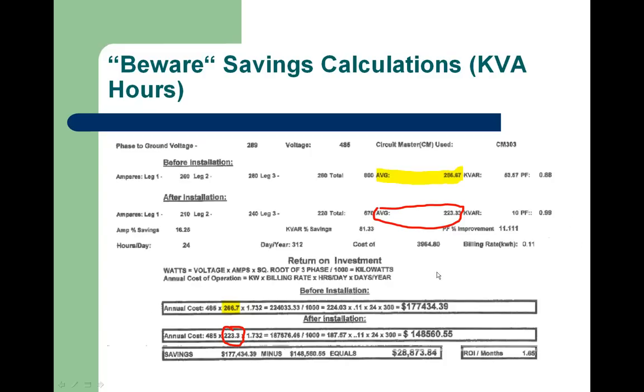The problem was that they were basing their savings on volt-amps, or kVA, and not watts or kilowatts. So the calculation that they have was based on this 266 amps, highlighted in yellow here, times the factor for three-phase. And you'll notice up here with the watts, voltage times amps times the root of 3 divided by 1,000 is kilowatts; they didn't show the power factor in there. So consequently, they calculated that this particular load would cost over $177,000 a year. And if they were to put in a capacitor bank, they would reduce their annual cost down to $148,000, which would be about a $28,000 savings.